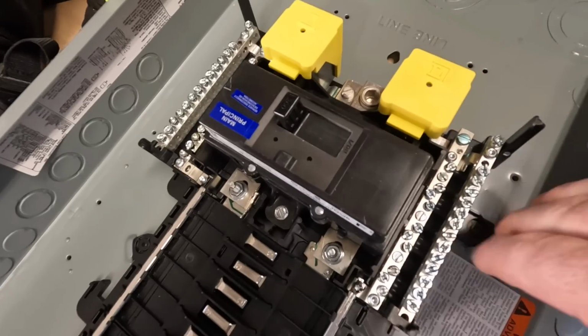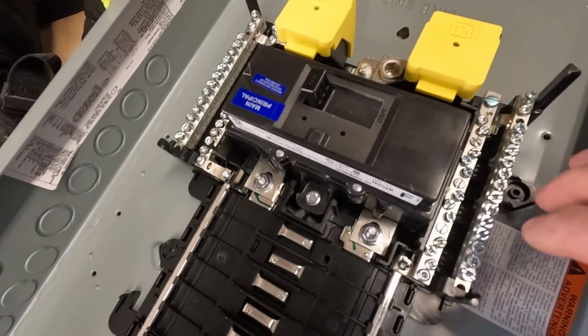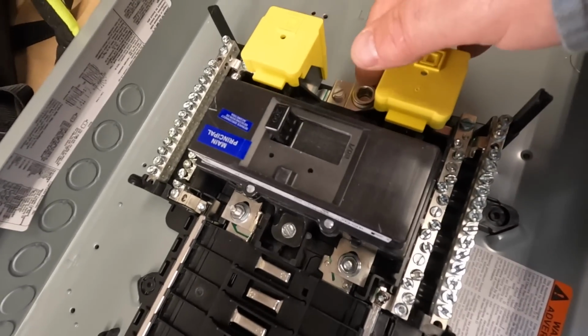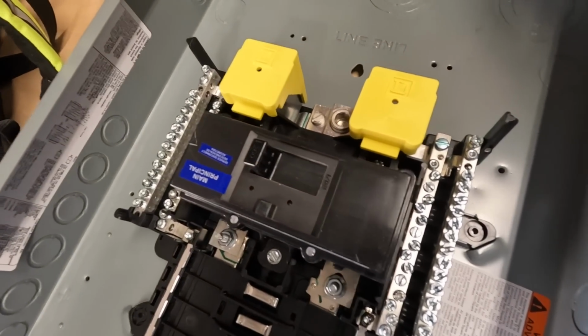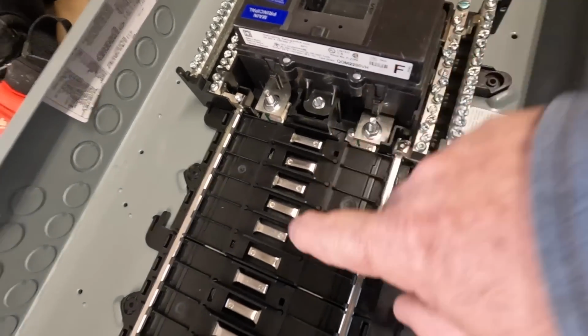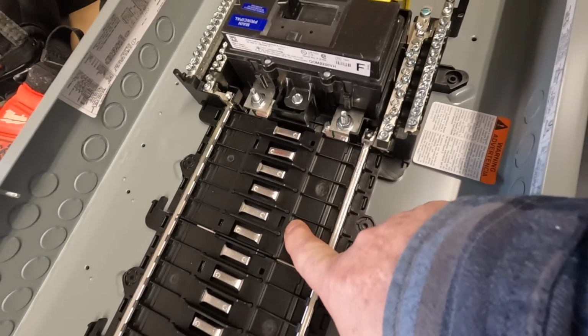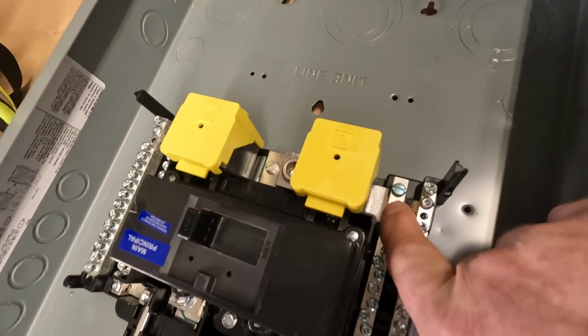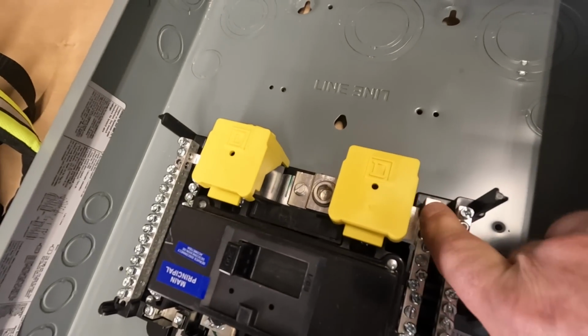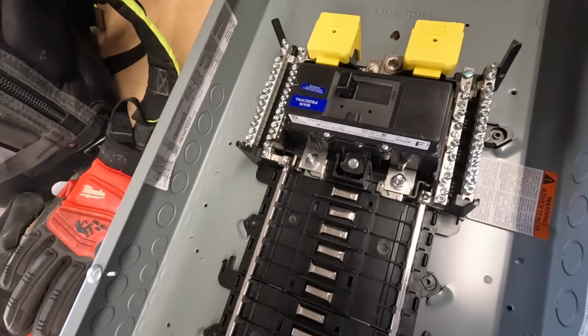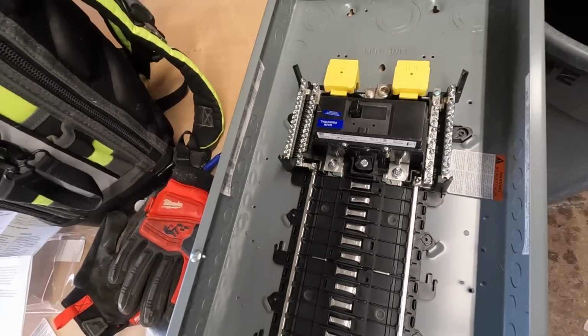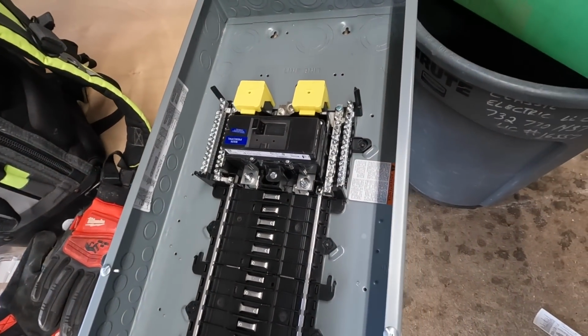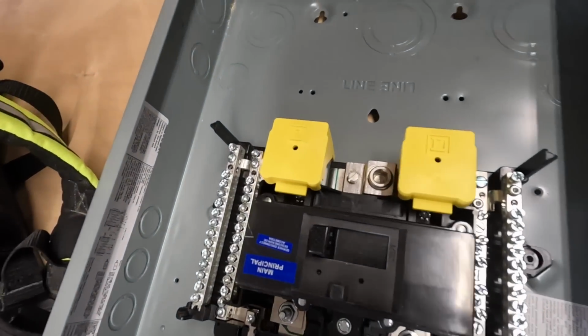And for clearing faults, the green wires and the bare wires are your equipment grounding conductors that come back to this terminal and then eventually back to the grounded conductor, which eventually goes back to the source, comes back on whichever leg is having the problem, and opens up and facilitates the circuit breaker to clear a fault. So that's why we put the main bonding jumper in the main disconnect of the house, only in this panel. Everything downstream from this 200 amp main breaker main disconnect panel, the grounds and neutrals are always isolated, so we don't have objectionable current flow on our grounded parts, and we can facilitate a ground fault situation more rapidly and clear the circuit breaker so nobody gets hurt.